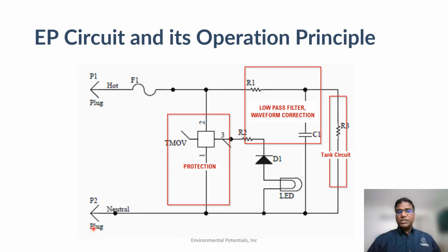I would like to take one step ahead and explain this scenario here. This is a TMOV that connects on a phase to the neutral, which dumps back to the neutral. But what matters most here is that the surge is not one single event. It is a ringing transient, a ringing decay function, like an exponential function, as we learned from school.